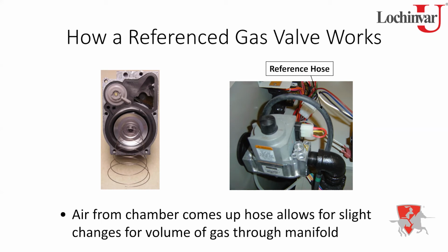So if you get a slight fluctuation in the air pressure from the blower, a voltage fluctuation, back pressure in the stack, something of that nature that might cause that pressure to change just a little bit, it's going to reference that to the gas valve, so your manifold pressure will change just a little bit to match it. So you're trying to maintain that balanced gas-air mixture going into the burner. Now, if you don't have your air shutter set correctly and it's just way off, this isn't going to compensate for that. So you make sure everything is set correctly, and then slight fluctuations during normal operation, this will help compensate for it.